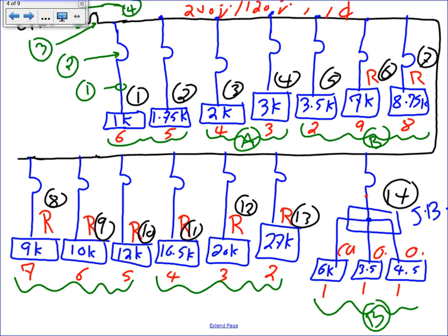Remember, we're done with the branch circuits. Note number 4, if you read it, is only for branch circuits. We're done now, and we're going to do the feeders. For doing the feeders, we care less how they're wired. We're going to add them all up based on where they sit in the column. Note number 4 does not mean anything when it comes to sizing feeders.